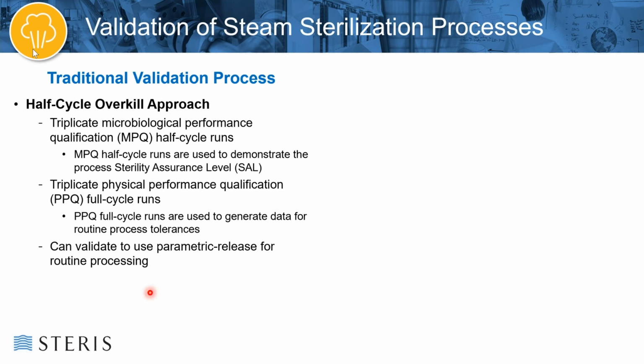And then one of the things with steam sterilization is that you can validate a process using parametric release, which essentially means that you don't have to wait for biological indicator testing for each production run. You can strictly go by the time and temperature and pressure data that you generate from the sterilizer strip chart to show that this process ran the same way as the processes that were done during the process validation, so we can be assured that the materials inside that run have been effectively sterilized.